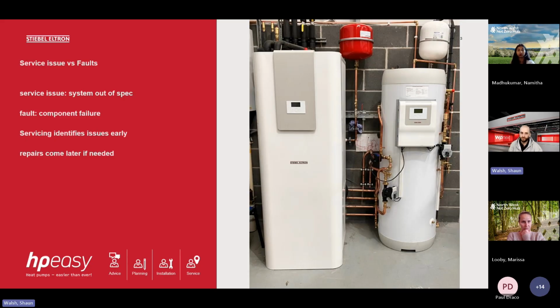So we have to define when we have a fault with the system, whether it's components or a service issue. Usually on a service, the main things you're going to be looking at will be air, dirt, pressure, and settings. They're the main four things, and that the system is actually still running. On a typical service, to make sure the machine is running as intended, you would set your hot water to the maximum of 60 degrees, let's say, and let the machine run and make sure it can achieve its maximum target temperature. You would then set it into heating mode, and set it to the maximum again to make sure that it can achieve the maximum that it needs to. When we do that, we're making sure that if the machine ever needs to run to these temperatures, the capability is there for it to do so.